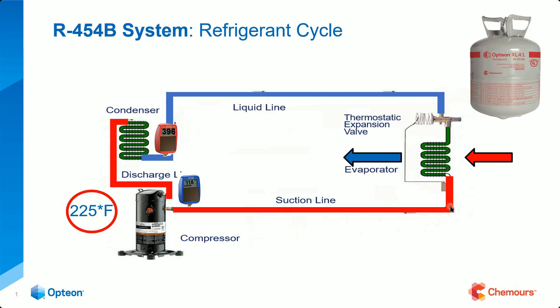It picks up that heat and we come down here. It takes that gas — this superheated vapor. Notice the line is larger because it's vapor; it expands, hence the name expansion valve. So we're heading down this suction line. The superheat here isn't going to be the same superheat as at the compressor. If you're talking to the equipment designer, they'll ask for superheat at the coil. If you're talking to a compressor manufacturer, they'll ask for your superheat at the compressor — typically known as total superheat.